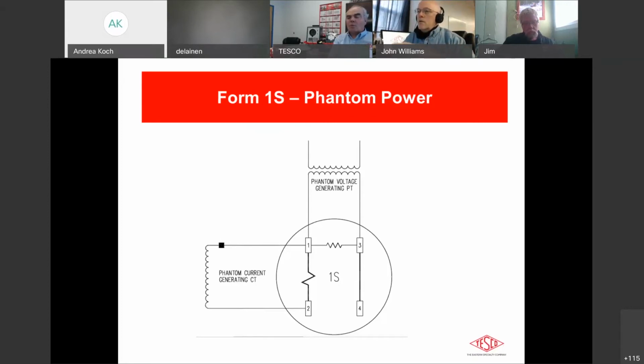Because these transformers are independent from one another and not tied to anything else, they can float at whatever voltage the potential transformer puts out. So that's how we can create that phantom power. The meter is just looking at what the voltage is across the voltage coil, what the current is across the current coil, multiplying the two of them together and measuring the phase angle between them and putting out a watt-hour reading. So we're doing the exact same thing here, but consuming much less energy in the application to the meter.